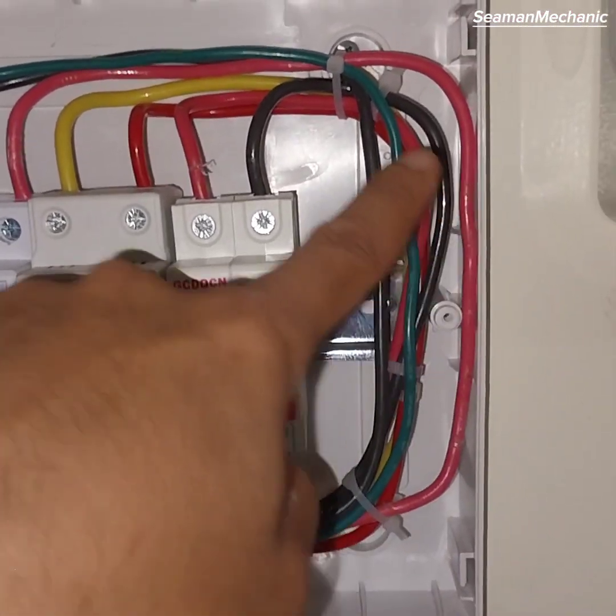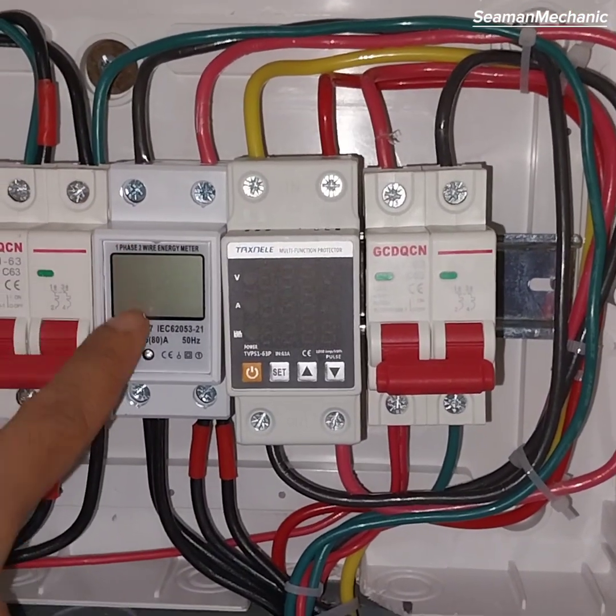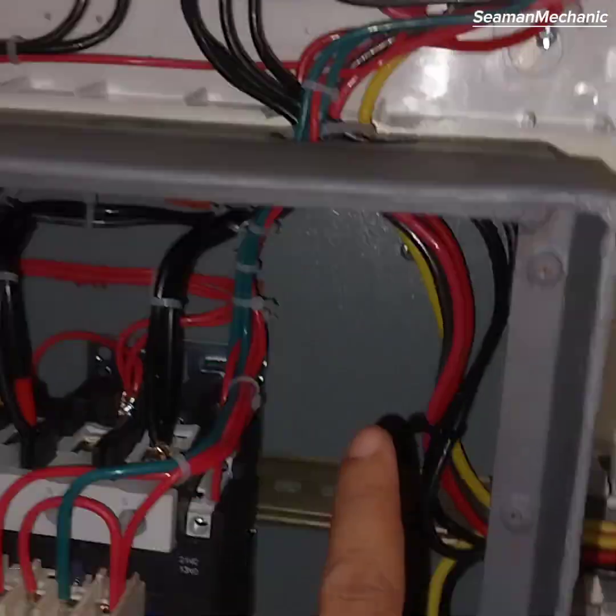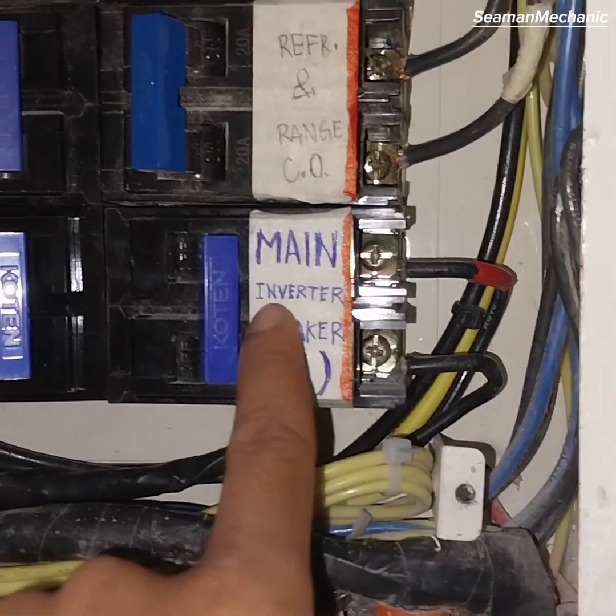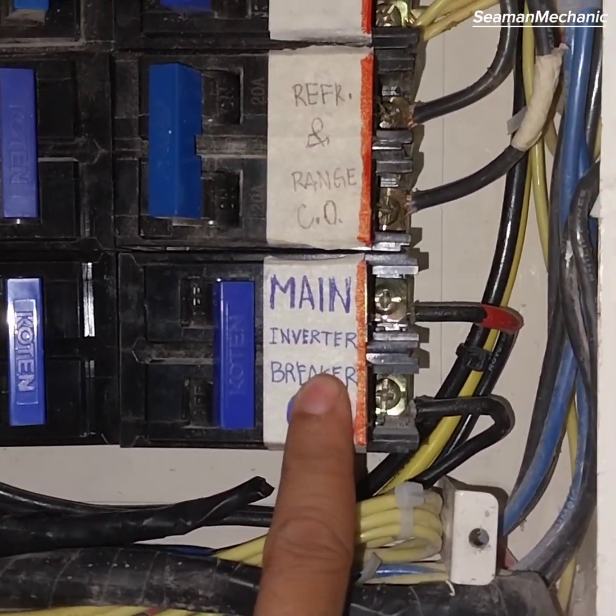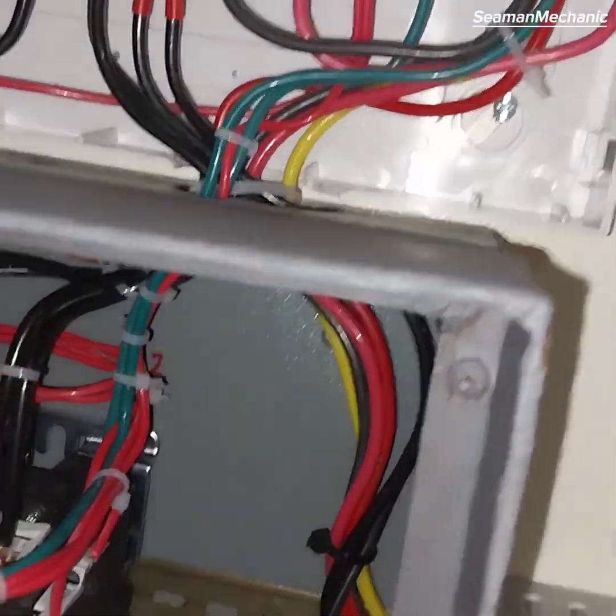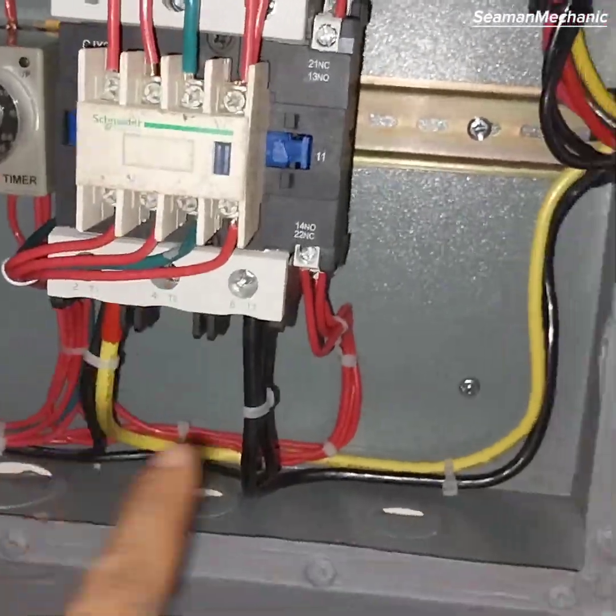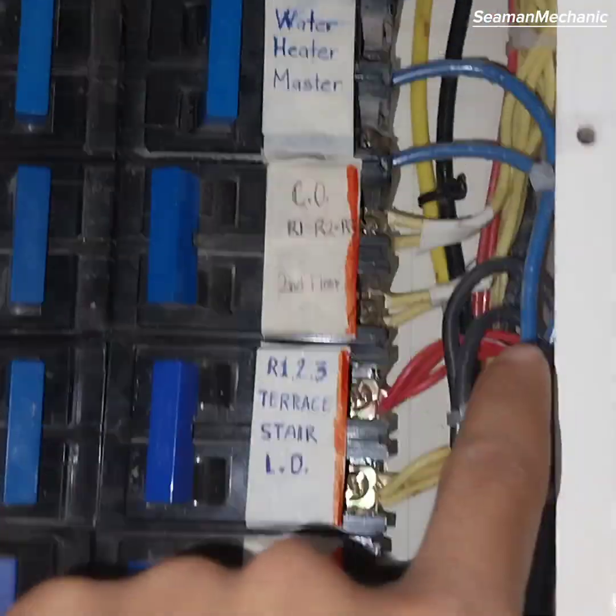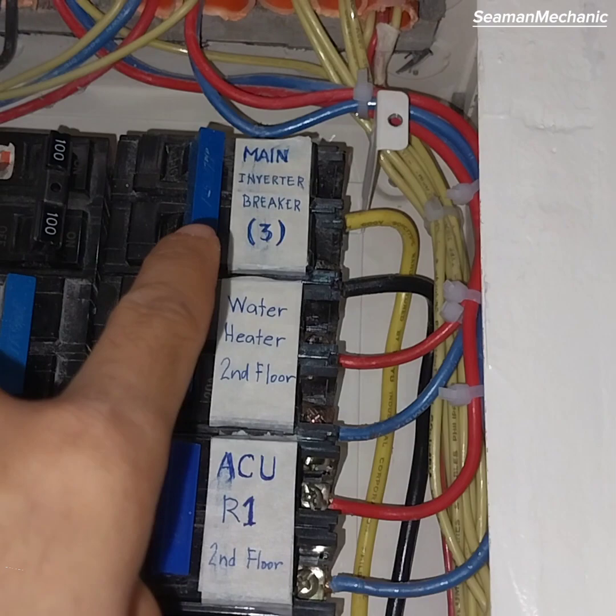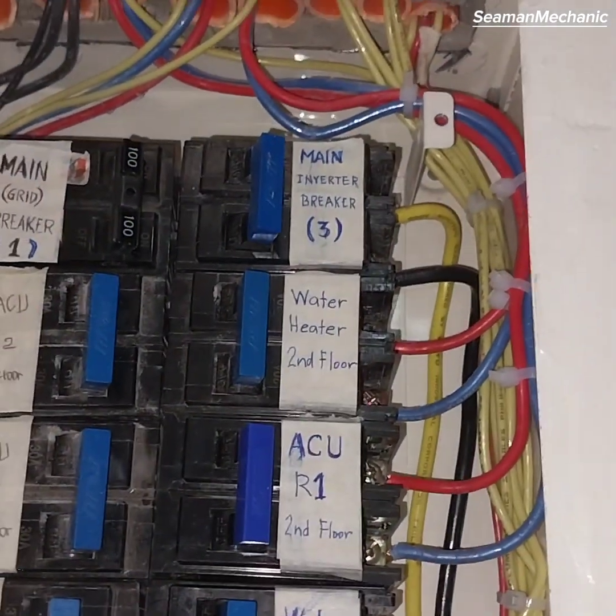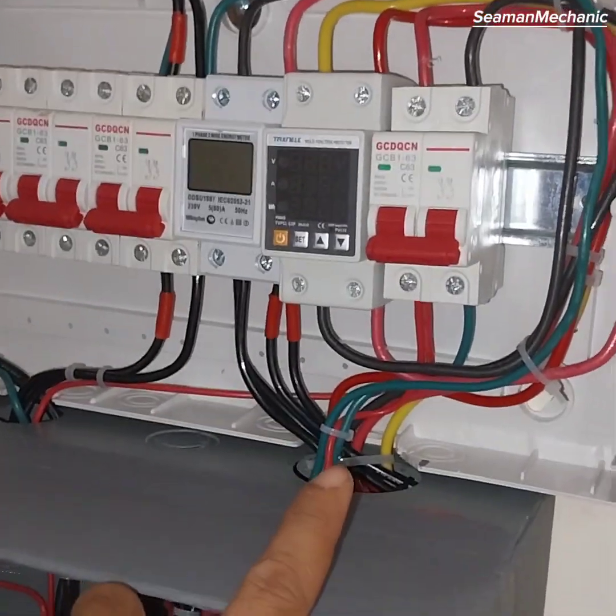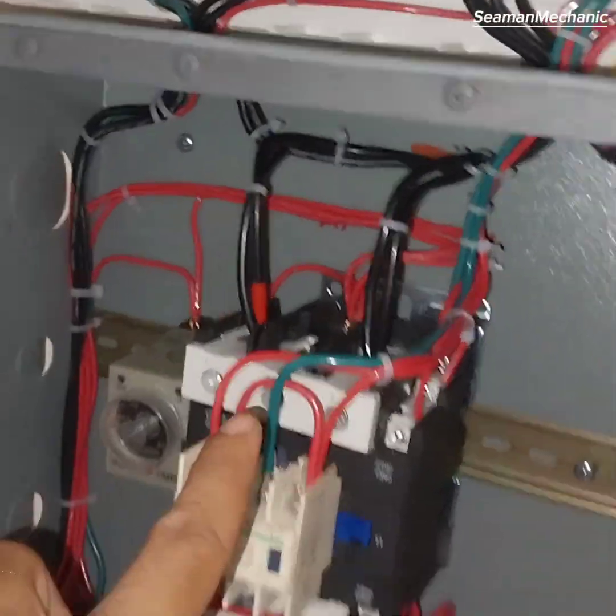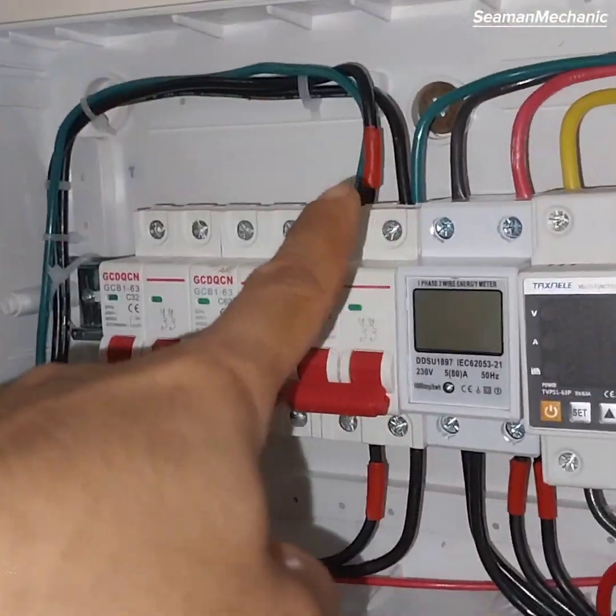Then to electronic energy meter. From electronic energy meter out to essential load circuit breaker in the panel box. For non-essential load, it will pass through magnetic contactor for auto load dropping during blackout and goes to non-essential load circuit breaker in the breaker panel box. The non-essential load circuit also have a bypass circuit breaker that can be used in case magnetic contactor fails.